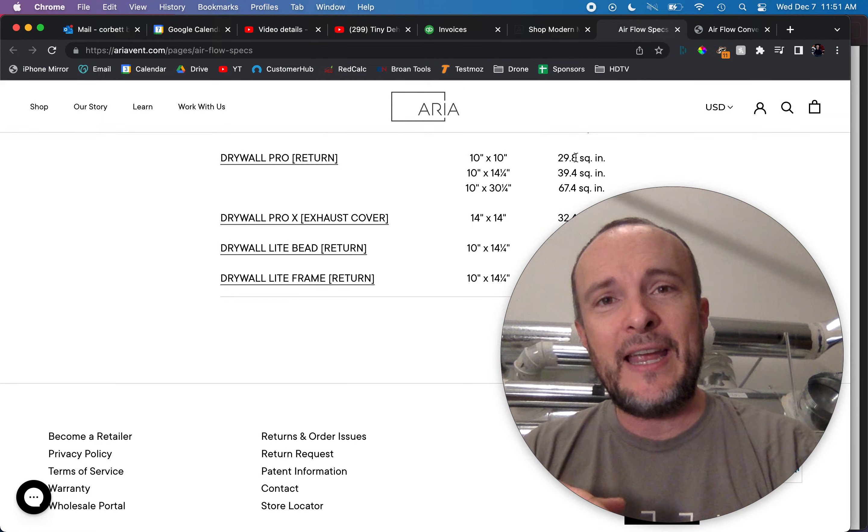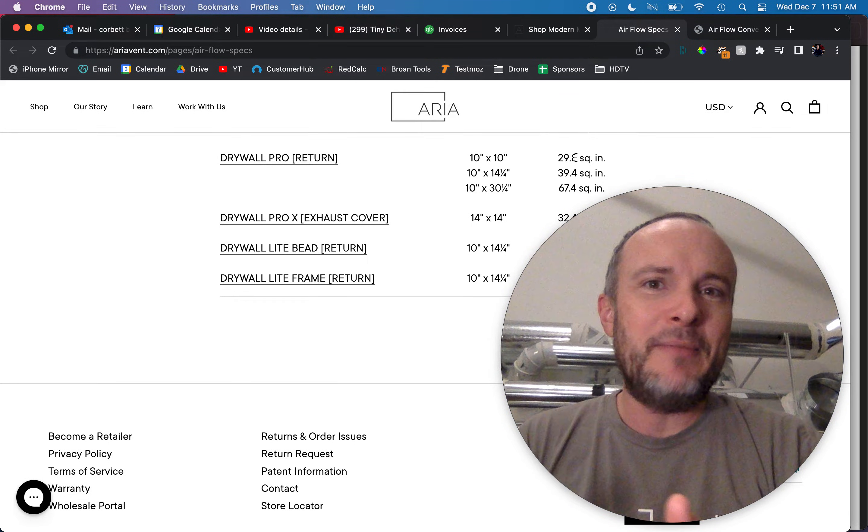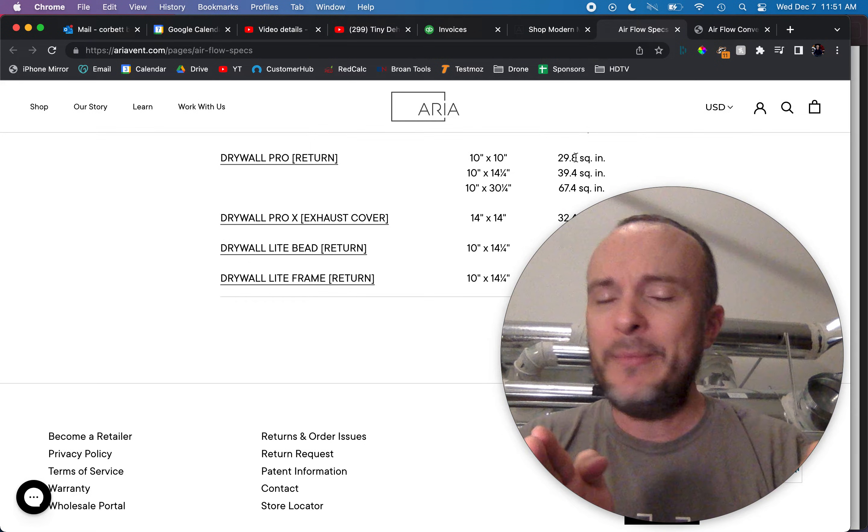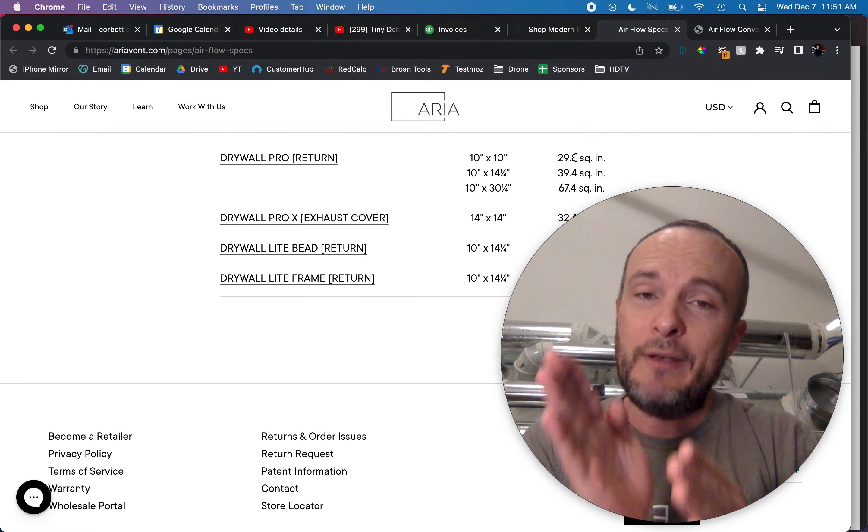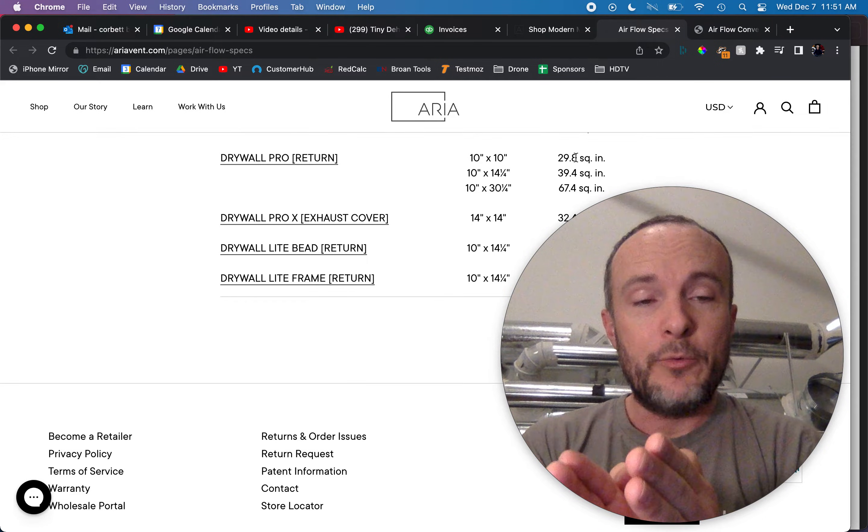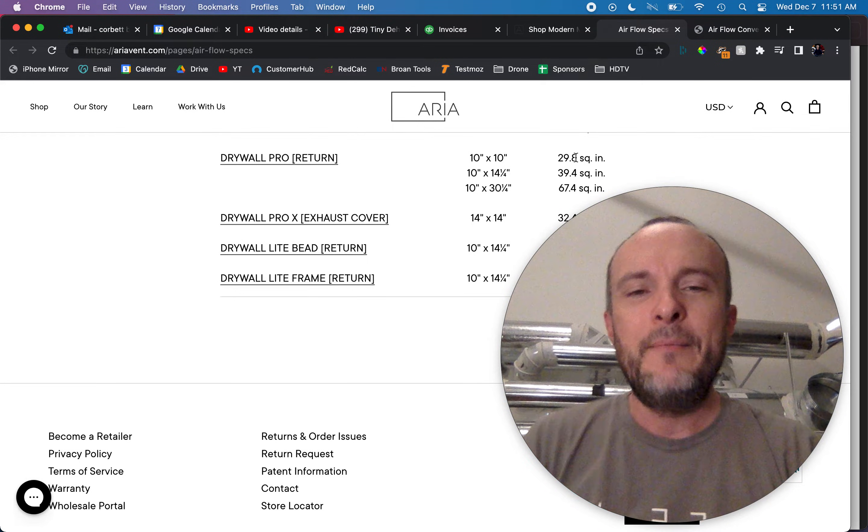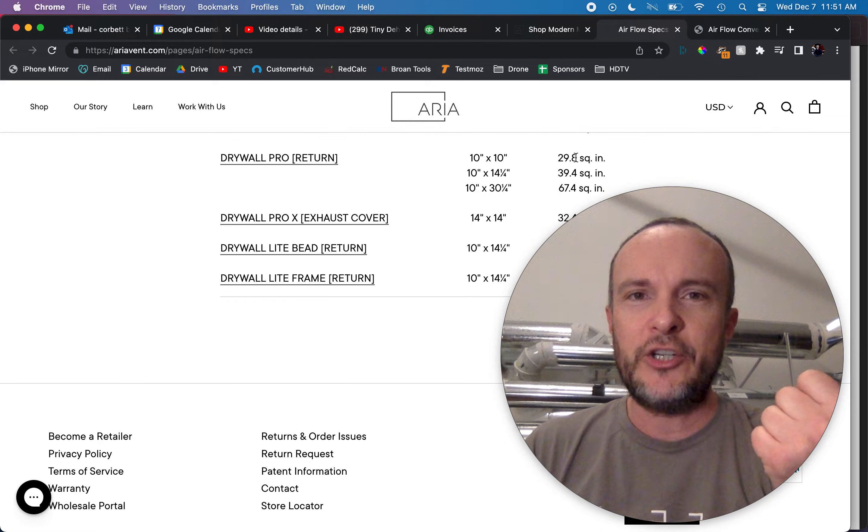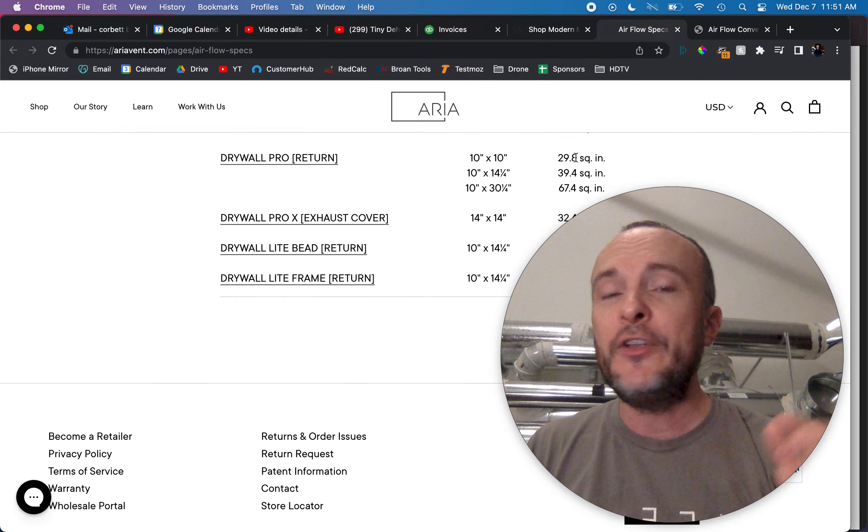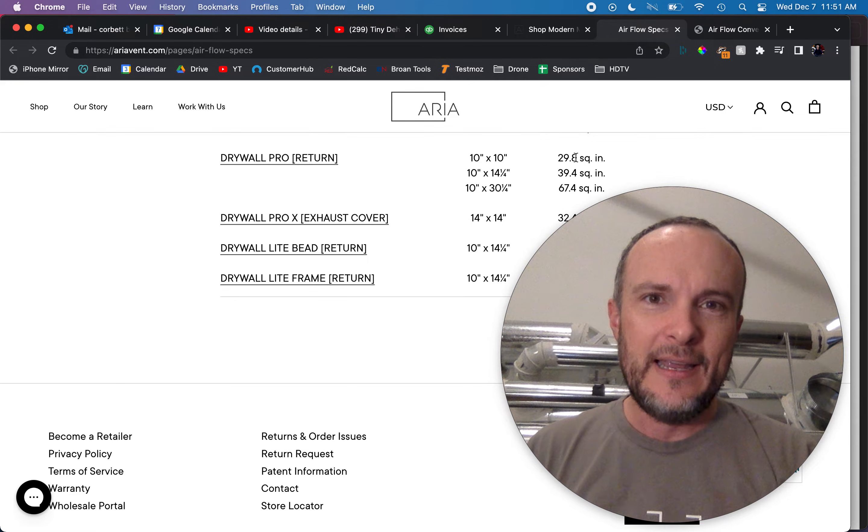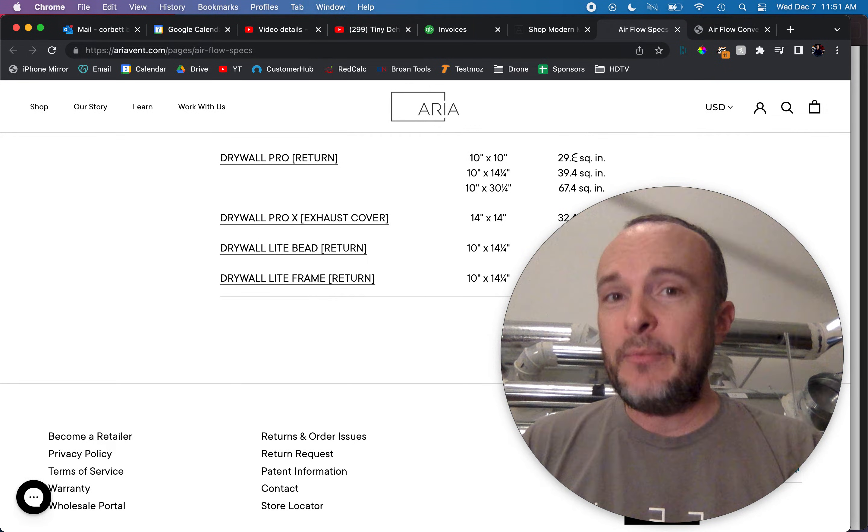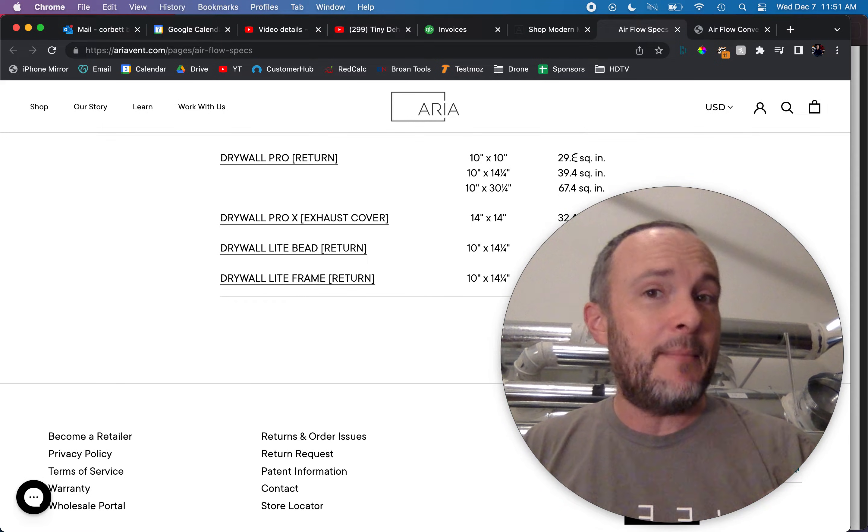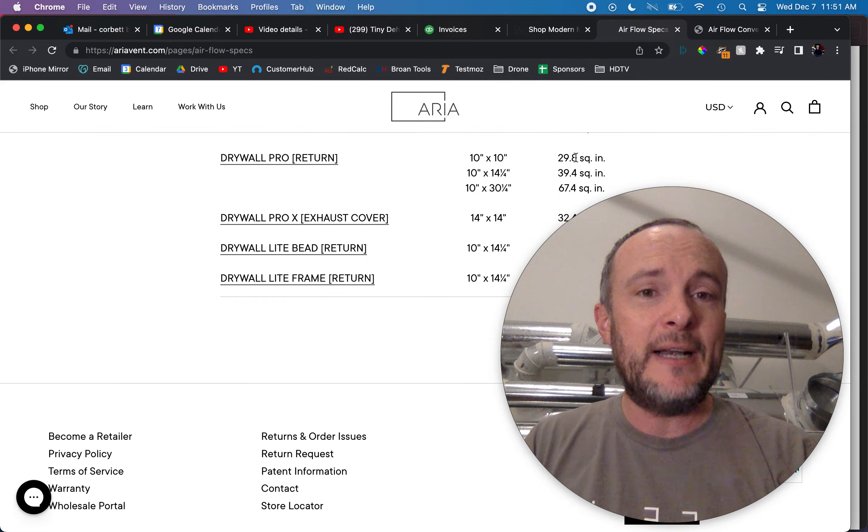So where on a supply ARIA thinks we might be looking at somewhere between 800 and 2600 feet per minute, which is not right. We're really looking between 500 and 700. On a return you want it to be about 250 feet per minute because number one you don't want to restrict the return. You want it to be as easy as possible. Number two you don't want it to hiss which is one of the byproducts of making it difficult. So if we want our returns to not make any noise, 250 feet per minute is good.